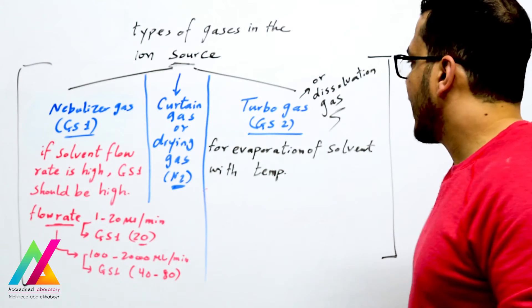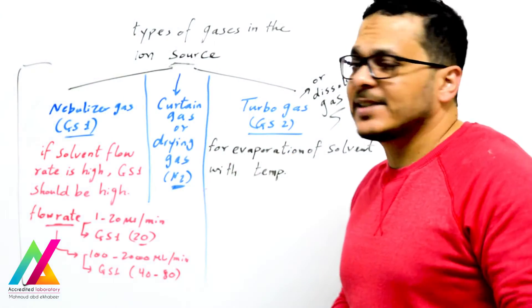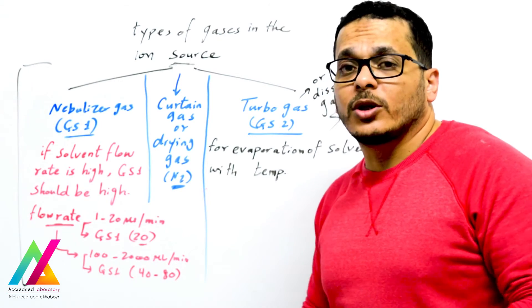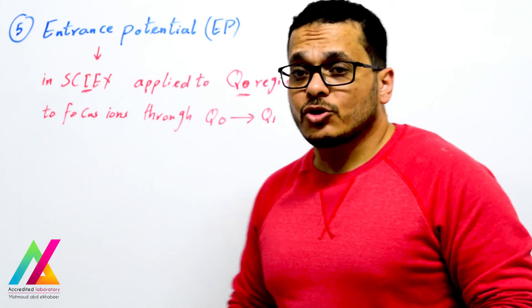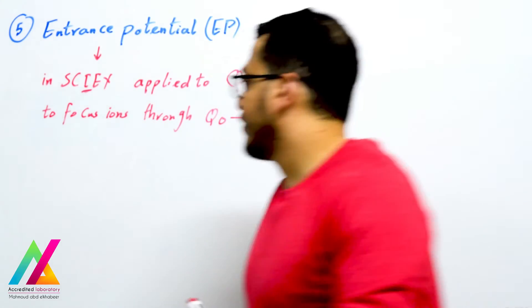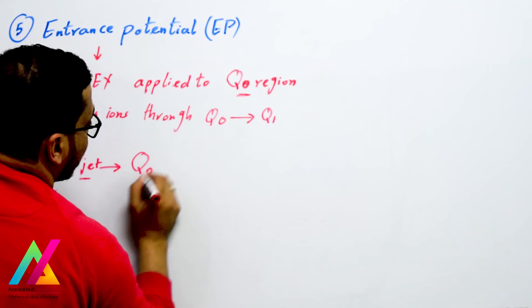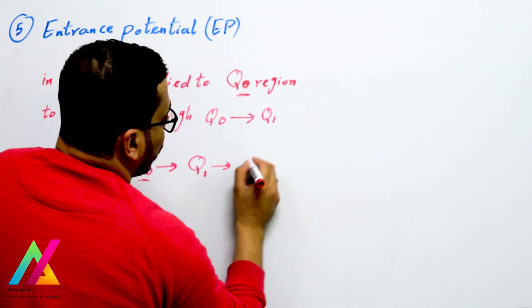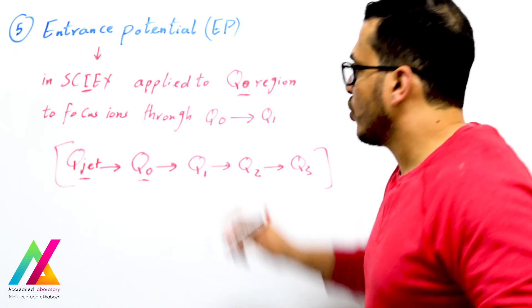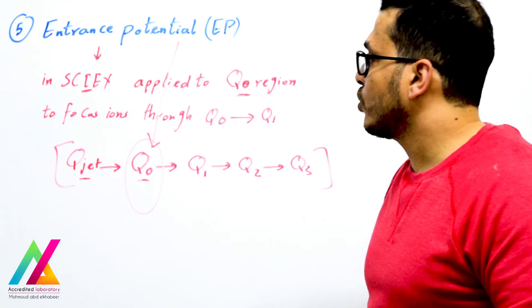Turbo gas or desolvation gas (Gas 2) is used for evaporation of solvent, also aided by temperature. Curtain gas, as discussed, prevents solvent droplets, neutral molecules, and solid particles from entering the mass analyzer. In AB Sciex instruments, there is also an entrance potential applied to the Q0 region. These instruments have a Q0 ion guide before Q1, whereas other instruments have only Q1, Q2, and Q3. The entrance potential is applied to the Q0 region to focus ions through Q0 to Q1. Q1 is a mass filter that selects precursor ions to be transferred to Q2, the collision cell. There is also a potential applied to Q1 called the rod offset, which must also be optimized.